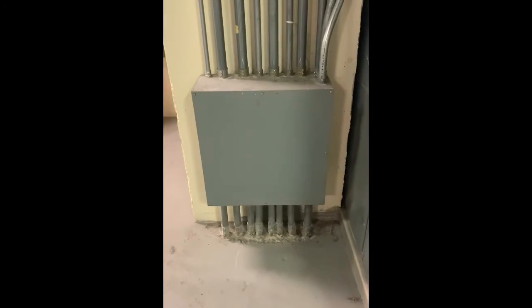Grounding. Okay, because this is the service entrance, this is where all the grounding is taking place. So all these conduits here are converging into this one splice box. From here, they continue down into the earth. Now, grounding can be accomplished in a variety of ways. The connecting of a ground circuit to a metal underground water pipe, like in your residence, is probably something you would be most familiar with. When you get into commercial applications, grounding includes the connection to building metal framing, concrete encased electrodes, or just a ground ring that is buried beneath the building, basically.